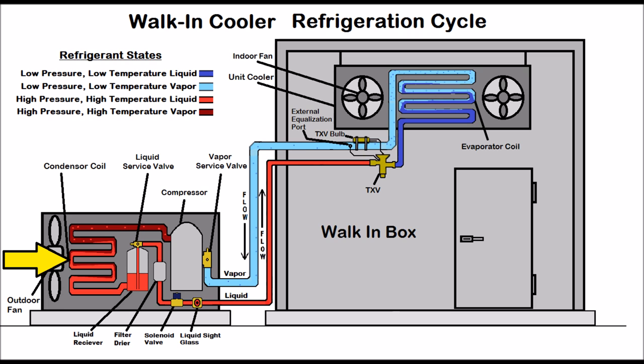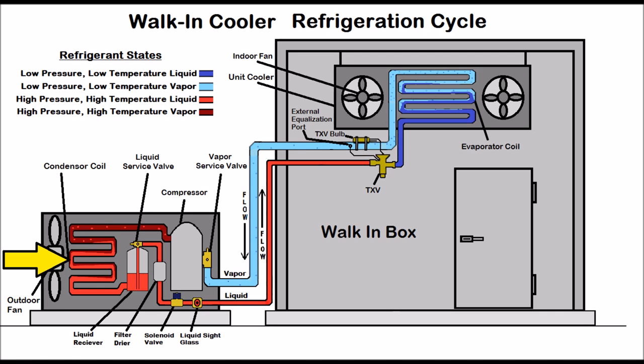Having a large saturated state in both the evaporator coil and the condenser coil is crucial to a refrigeration system working properly. You have to have complete vapor heading into the compressor — you want to make sure that you don't have any saturated refrigerant or straight liquid heading into the compressor. It has to be complete vapor only.